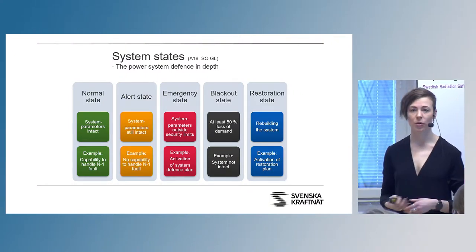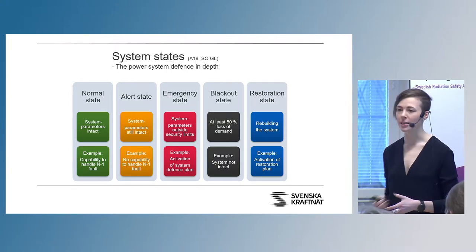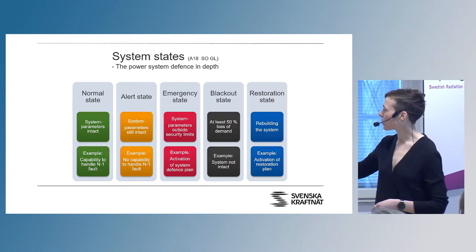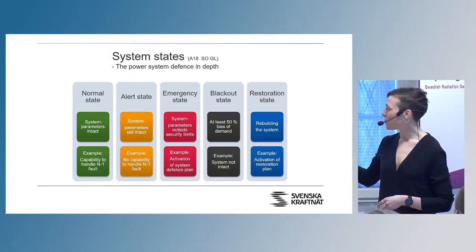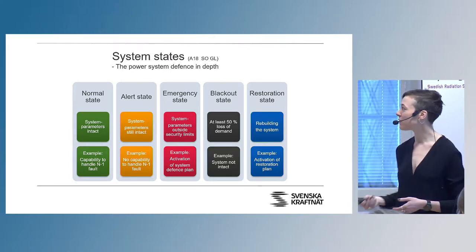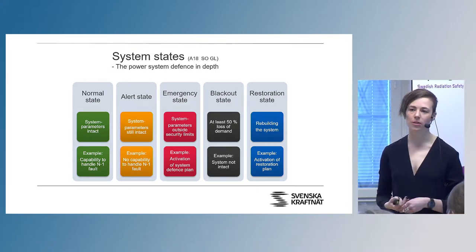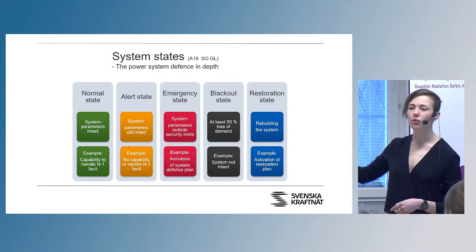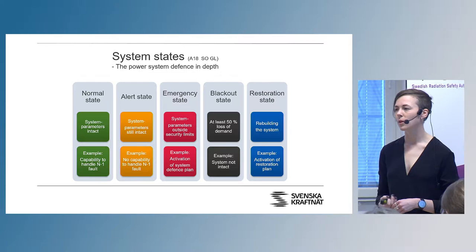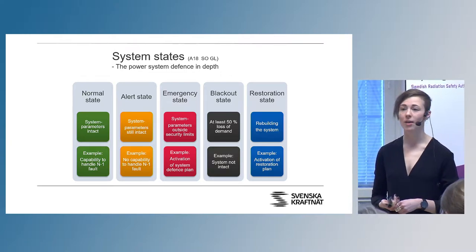How do we manage this? We use a method called defense in depth, which the nuclear power industry knows very well. It's a state-based approach: you have the normal state, alert state, emergency state, and a system defense plan. If all three layers of defense in depth fail, we have a plan to restore and take it back to normal state. System challenges with less margin will make us move faster between those system states.